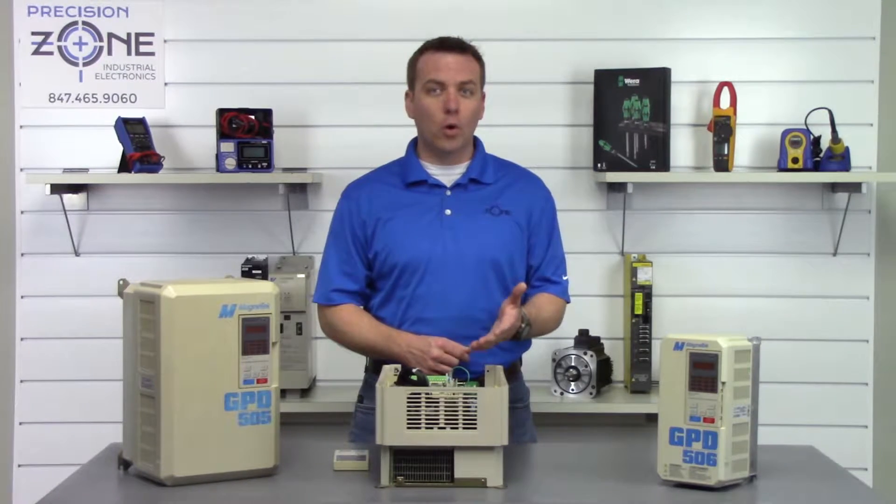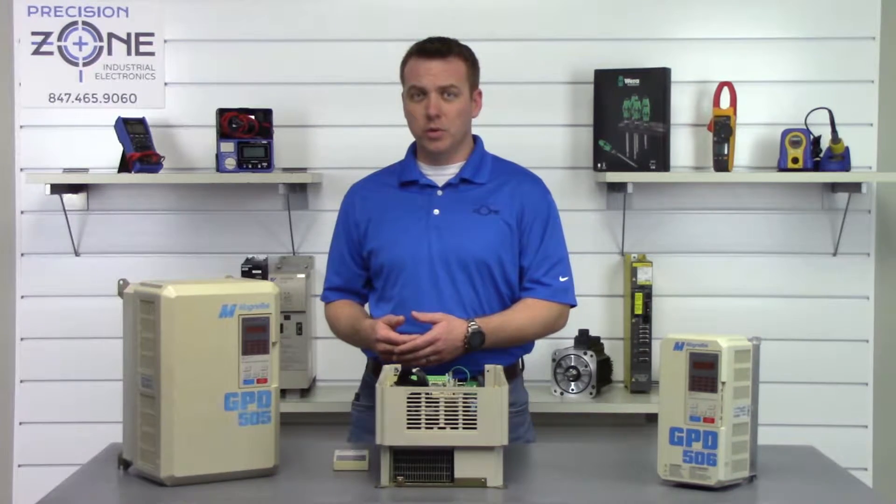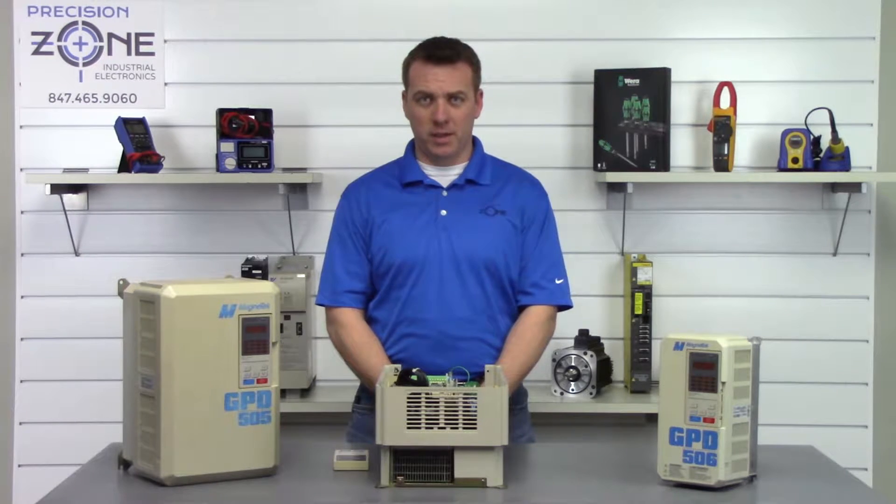Overcurrent alarms normally point to low insulation on a motor or the motor cables, and you'll want to use an megohmmeter to verify the integrity of the insulation.